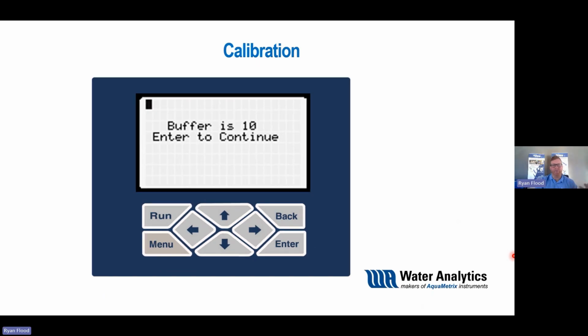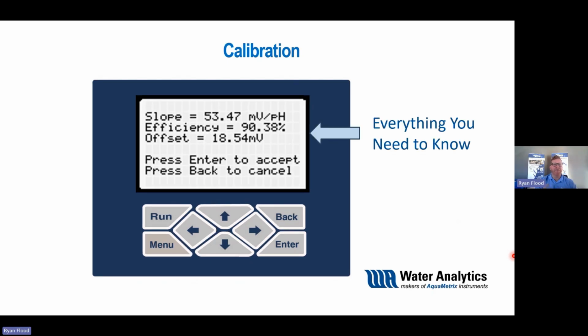And then here, I didn't update that screen. It should say, put it in buffer solution 4 or 7, one of the other two standards that we have. Once it detects that, you're going to go ahead and hit continue. And then it's going to go through it. And this is really everything you need here at the end. You're going to look at your slope and your efficiency and your offset. And what we would really kind of highlight here is this helps you identify how your sensor is behaving.